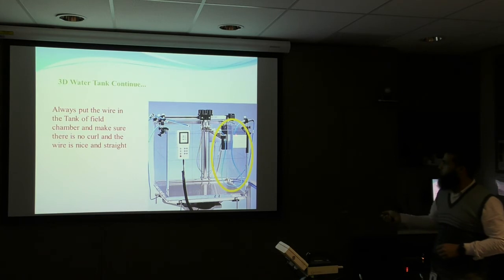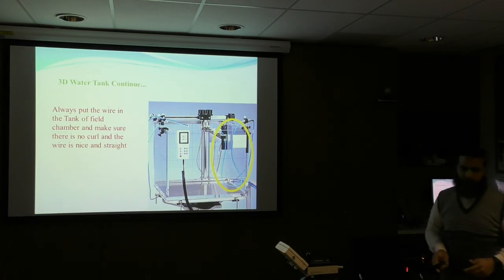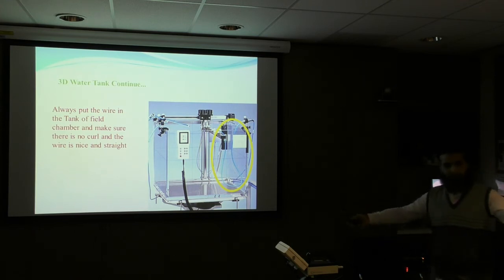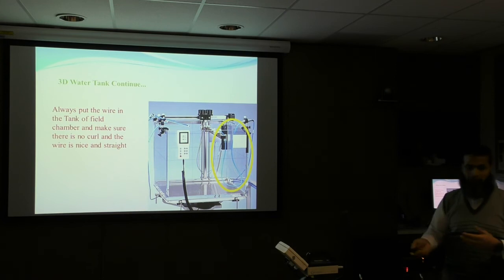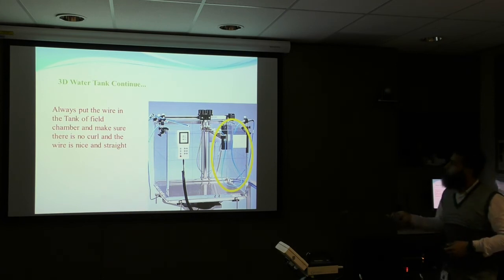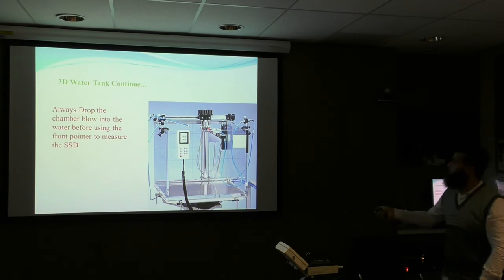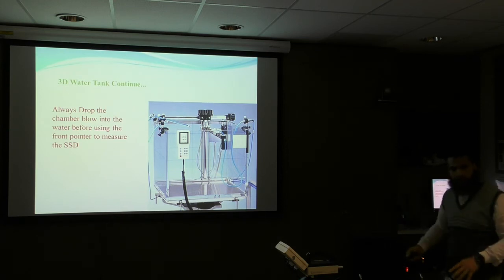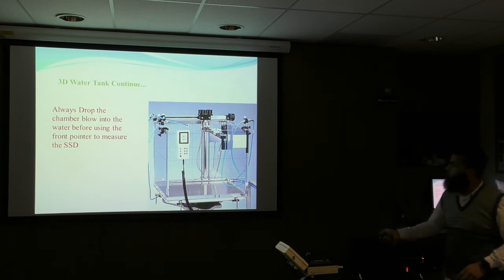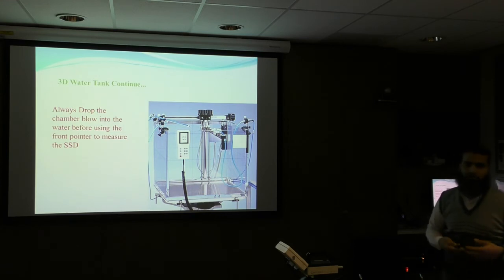When you put the wire in, just make sure the wire is all the way in. This wire could affect your readings - when you're doing a big field, the wire is actually in the radiation and it is producing some signal, a very very low signal, but you can see the difference when comparing very precise readings. My recommendation is to put it all the way in, because when you go down, there is no stretch on the wire. This rod goes up and down as well as laterally and in all three directions, so it needs sufficient space to travel all around.